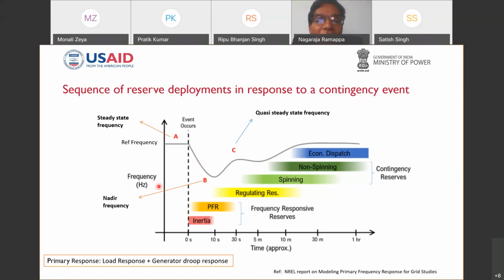Next frequency, what we talk about here is the point B, which we call the Nadir frequency. That is, what is the minimum frequency the system will go to, so that the under frequency load shedding will not happen, and the frequency starts improving. That is what will happen because of your primary control, that is the governor droop characteristic. Then comes your secondary control, that is the automatic generation control, which is the regulating reserve. And then come your various non-spinning reserves, economic dispatch, unit commitment, and all those things. What is important for system frequency control is the Nadir frequency and the quasi-steady-state frequency we are able to maintain. That is very, very important. Next, please.